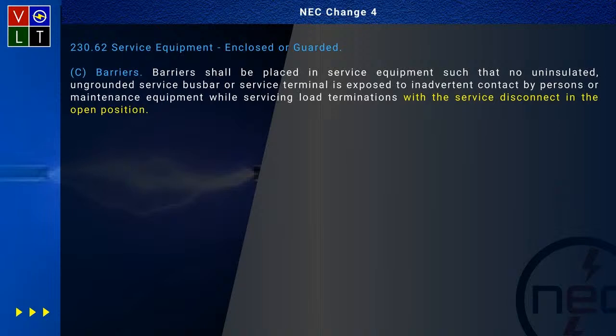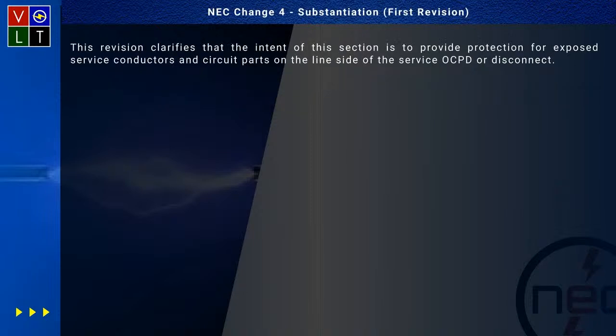So it's more of a safety thing. That's really, in my mind, it's in compliance with 70E the way I look at this. And what they tell you here, they're telling you the revision clarifies that the intent of this section is to provide protection for exposed service conductors and circuit parts that are where? On the line side of the service disconnect or overcurrent protection device or disconnect.